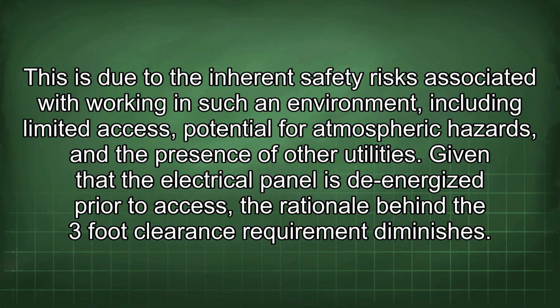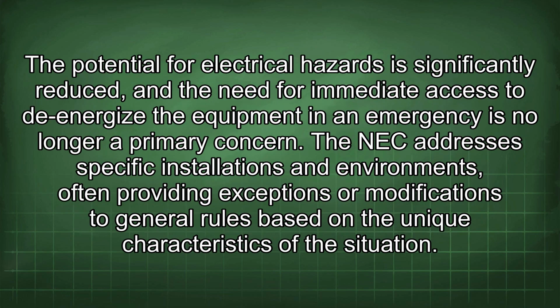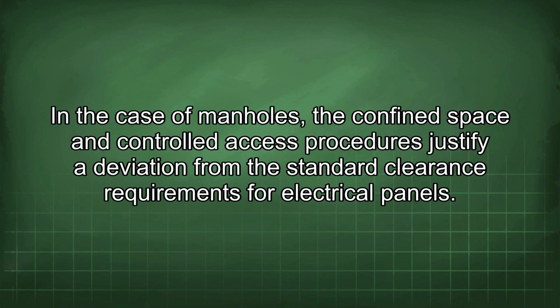Given that the electrical panel is de-energized prior to access, the rationale behind the 3-foot clearance requirement diminishes. The potential for electrical hazards is significantly reduced, and the need for immediate access to de-energize the equipment in an emergency is no longer a primary concern. The NEC addresses specific installations and environments, often providing exceptions or modifications to general rules based on the unique characteristics of the situation. In the case of manholes, the confined space and controlled access procedures justify a deviation from the standard clearance requirements for electrical panels.